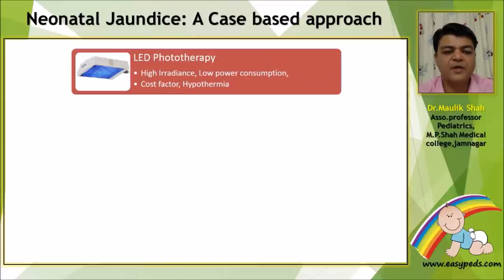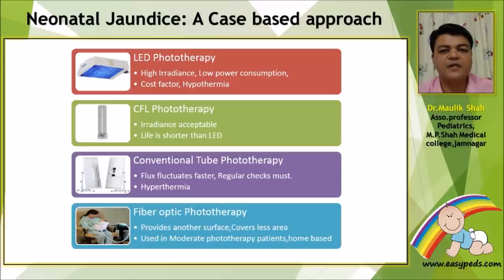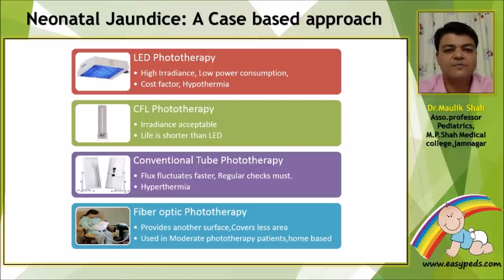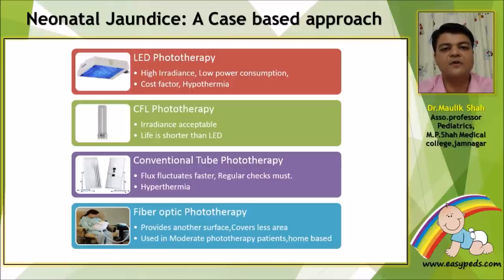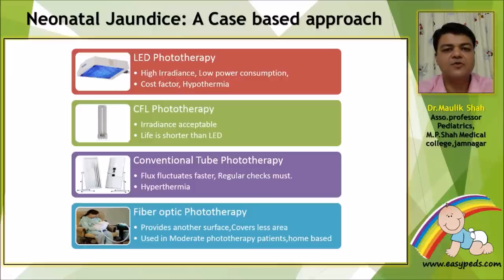There are four varieties of phototherapy currently available. First is LED phototherapy, which is highly available, has high irradiance, works on very low power consumption — that is its unique selling point. However, one must consider the higher cost factor, and note that LED is a cool light, meaning the baby is likely to become hypothermic under it. So an additional heat source like a warmer should be provided.